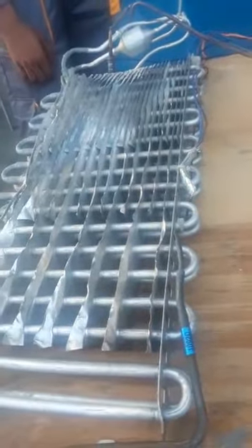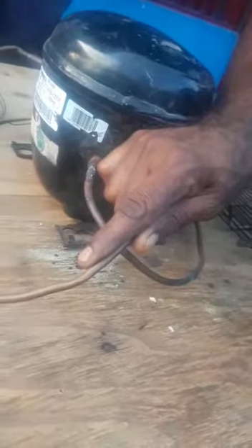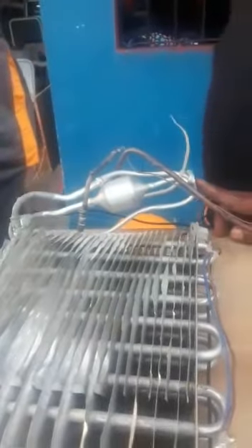But it cannot leave the evaporator as low pressure, low temperature liquid. It has to change to low pressure, low temperature gas before it leaves the evaporator and goes back through the suction line. In the accumulator here, the low pressure, low temperature wet gas is dried out before it goes back into the compressor through the suction valve as low pressure, low temperature gas.